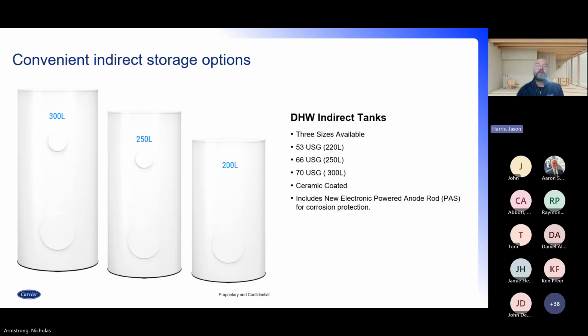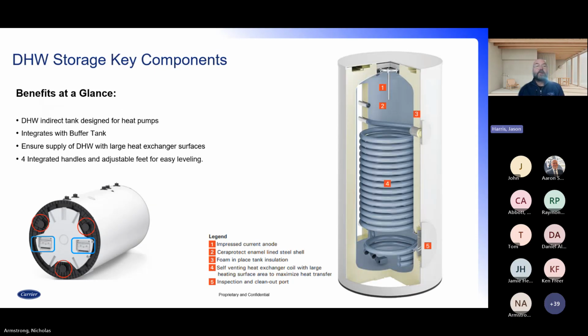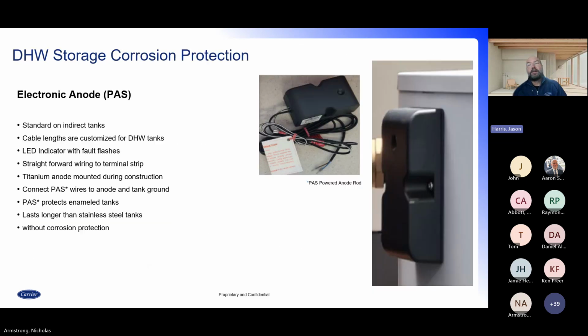We have three sizes: 53-gallon, 66-gallon, and 70-gallon. These are ceramic coated with a powered anode system for corrosion protection. Next. Integrated carrying handles: there are two sets of handles to make transport easy. It has a large coil for better heat transfer. This tank has been specifically designed for heat pumps to provide better domestic hot water recovery in a heat pump application. It is well insulated with thick foam insulation, it is enamel coated, and it has integrated clean out ports.